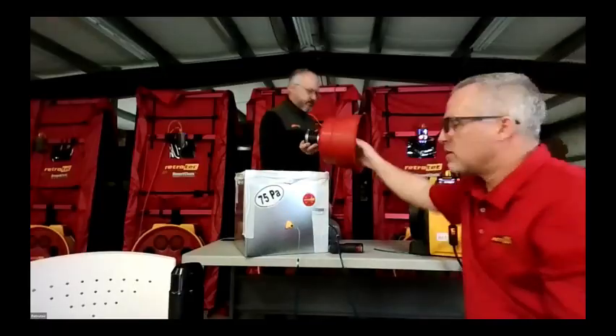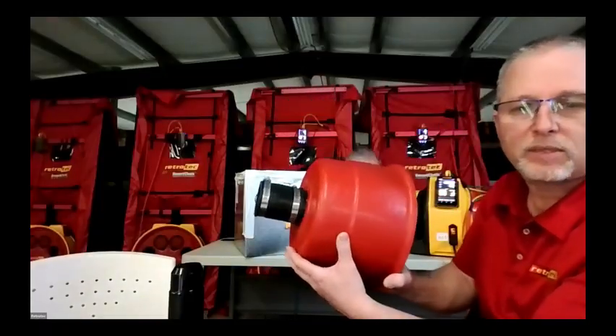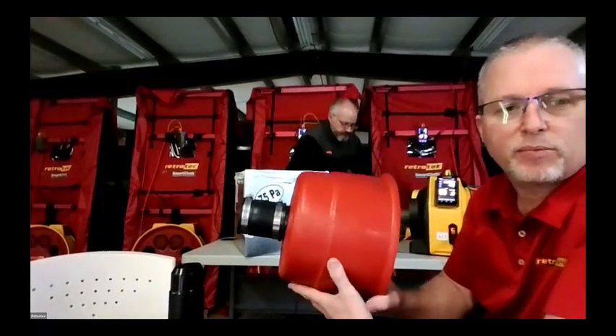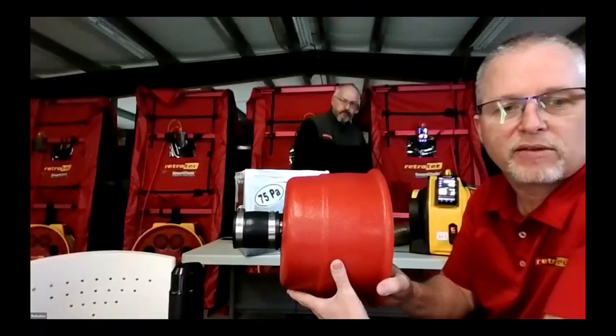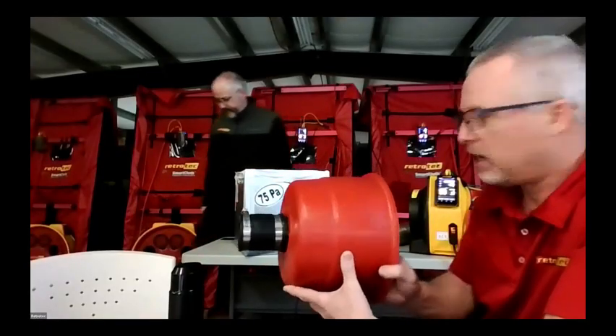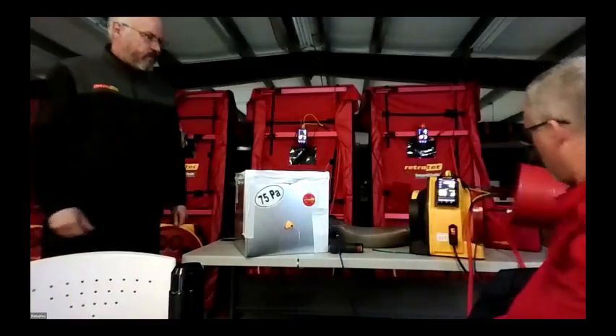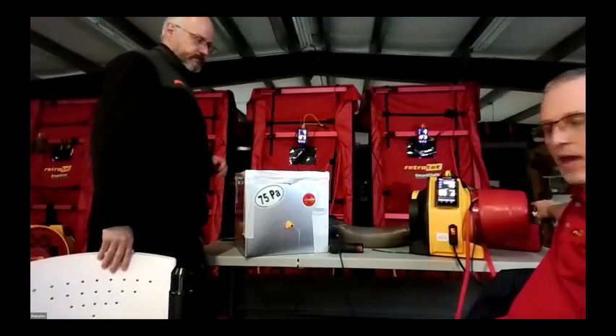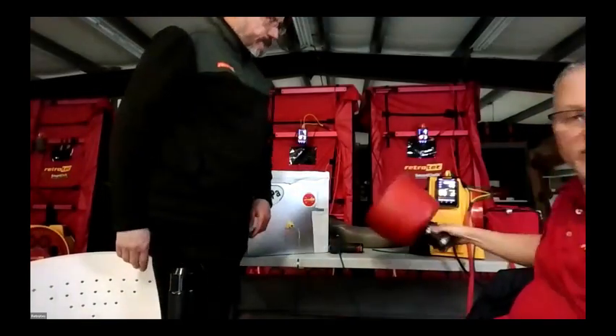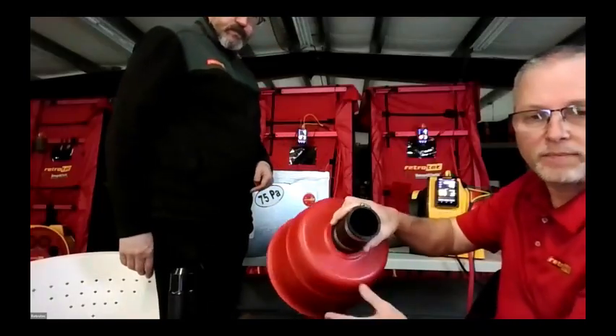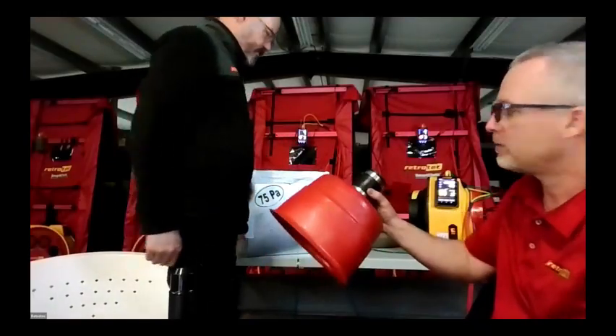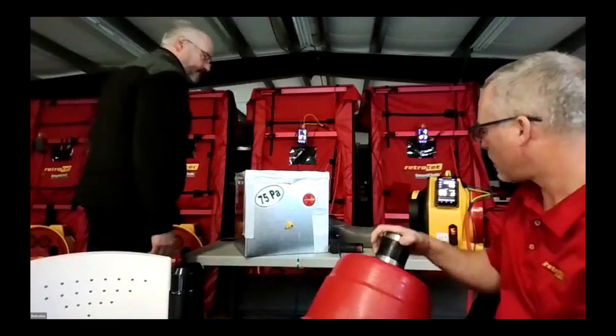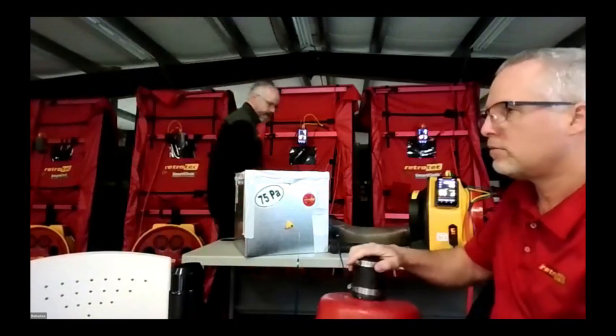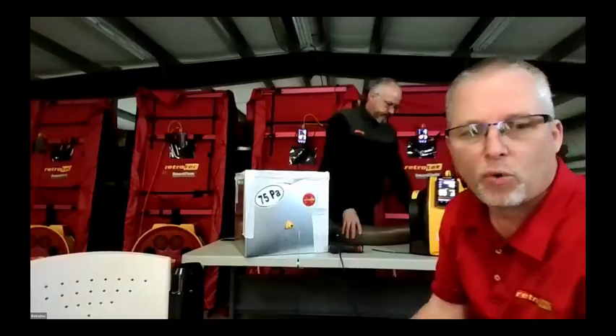And about the depressure. This is so you can depressurize the duct system. Like I said, if you pull negative pressure on a duct, then you can check for leaks that way with the smoke. It connects on the inlet of the fan, and then the flex duct will connect to the collar and be able to depressurize for you.